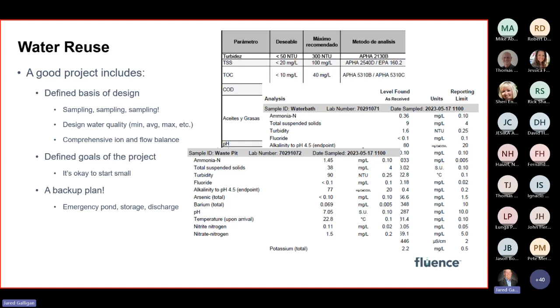Some of the best reuse projects we focus on, or when we identify a good candidate, are ones that give us consistent water quality coming in. Ideally that's true with any water treatment system, but it's especially true with a reuse system. We want a narrow, consistent window of what that water quality is, which goes back to the earlier recommendation of doing large amounts of sampling, multiple rounds, identifying when the best time is, when your plant's worst conditions are, and sampling to try to build out the total range of water quality you might see.